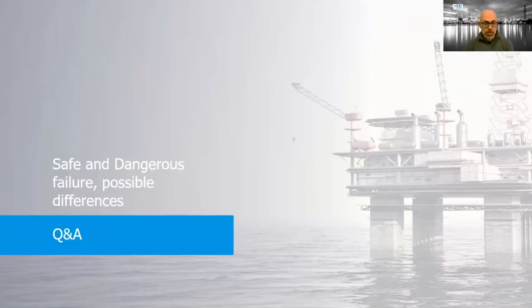Yes, I think that it's mandatory to have a safety loop. It is mandatory to have a SIL certified power supply. You have shown previously that it takes a big weight on your total SIL percentage, a few percent, if I remember around 6-7%. So it is definitely important when you are calculating your SIL loop level. Okay, well, Andrea, next question.